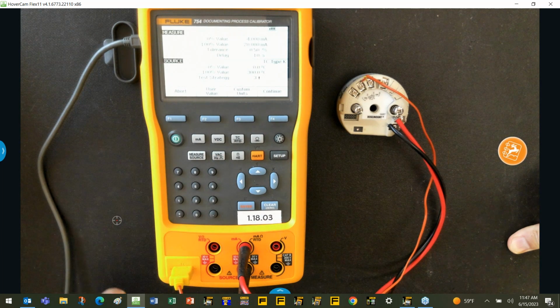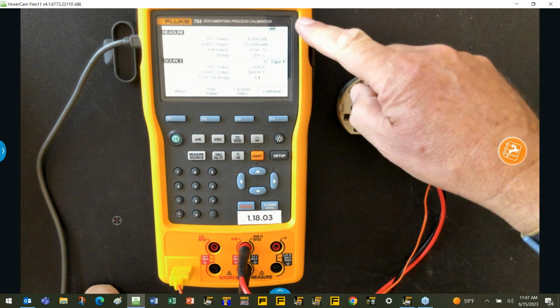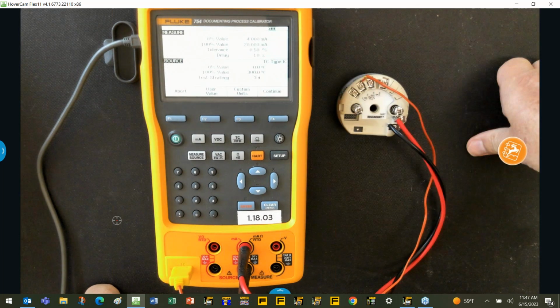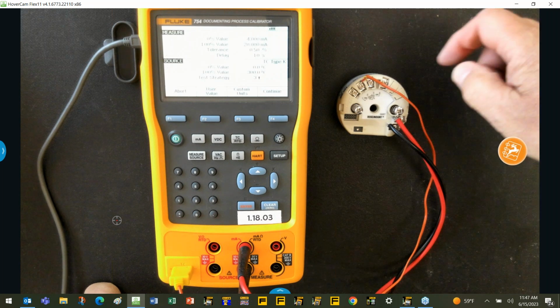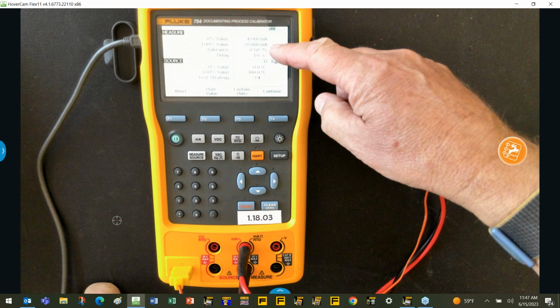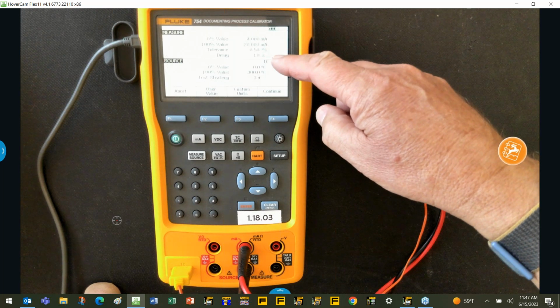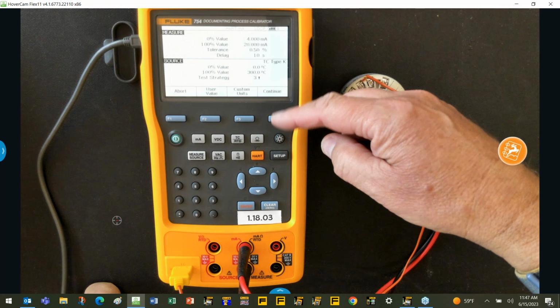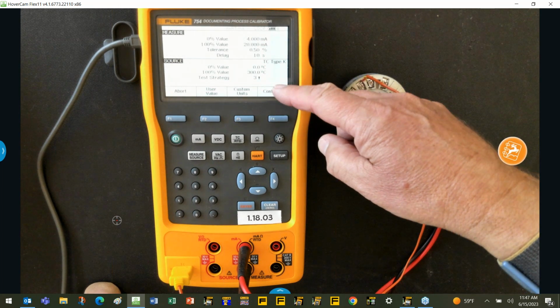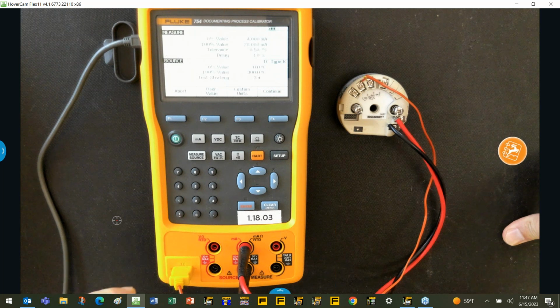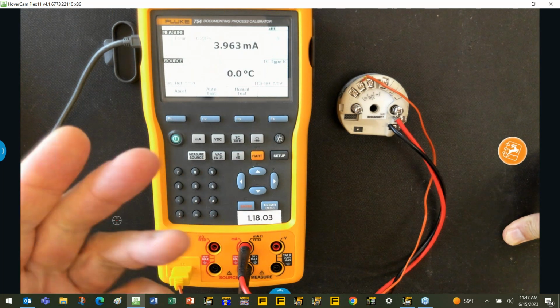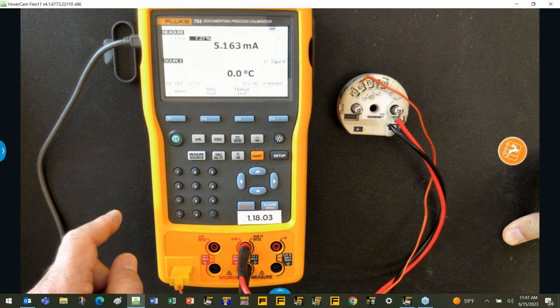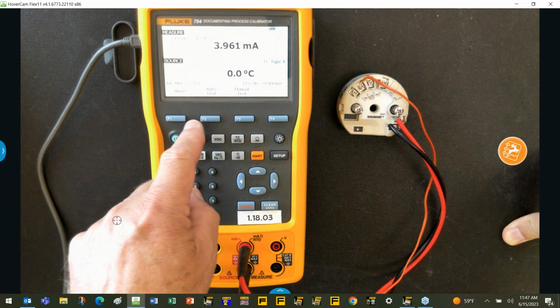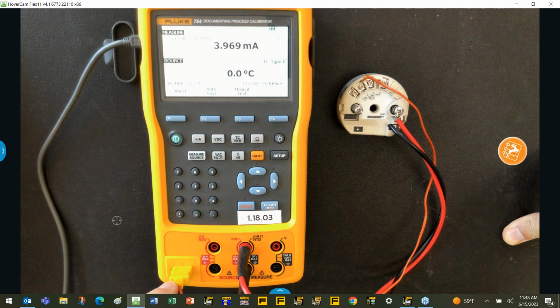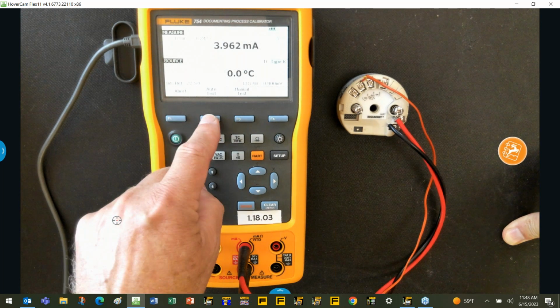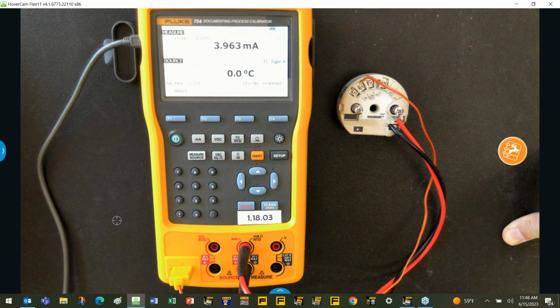Okay, now here's the screen for the calibration setup. Notice everything has automatically been put into the calibrator from that downloaded task. So we know we've got the 4-20 output. We're going to set the tolerance at 0.5%, delay 10 seconds between test points, a 3-up test, and it's 0 to 300 degrees C in this case. Okay. Now we're at the calibration screen. So we're going to go ahead and auto test, in this case, because we're going to automatically send the type K millivolt signal. So hit auto test. At this point, it'll do a 3-up test.